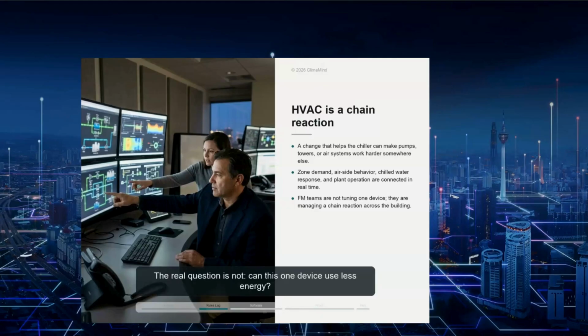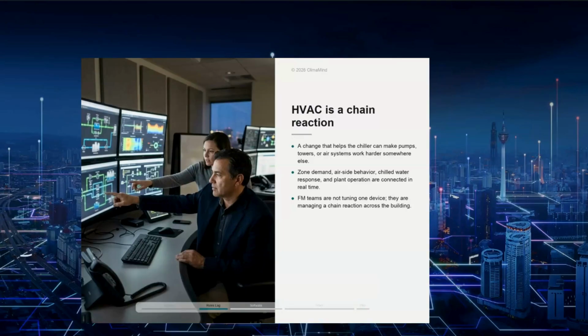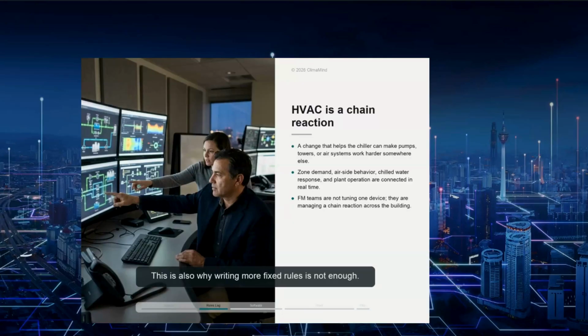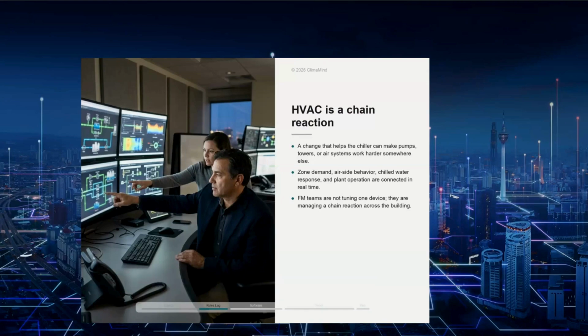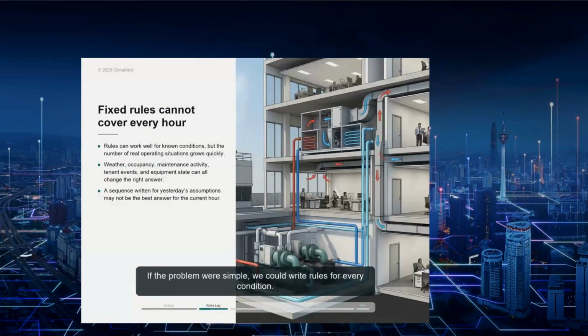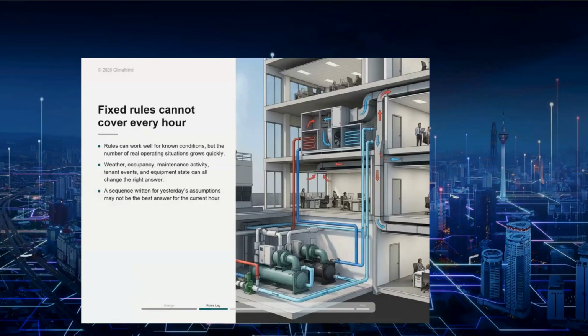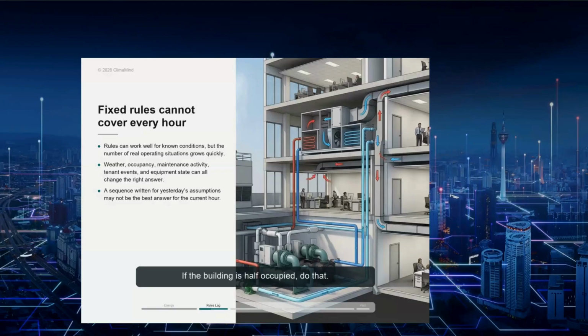The real question is not, can this one device use less energy? The real question is, can the whole system serve the building with less energy right now without creating a problem somewhere else? This is also why writing more fixed rules is not enough. If the problem were simple, we could write rules for every condition. If it is hot outside, do this. If the building is half occupied, do that. If one chiller is running, use this sequence. If two chillers are running, use another sequence.